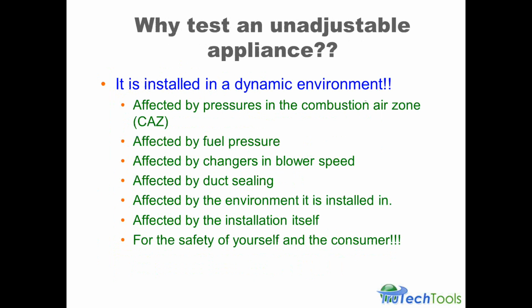Another question we often get is, why would I want to test an appliance that's unadjustable? Many times people consider that, especially residential warm air heating systems, furnaces, are really plug and play, and that couldn't be further from the truth. In addition to having to be installed correctly with the right kind of airflow and the right fuel pressure, real basic issues, you also have to recognize that the equipment is installed in a dynamic environment. There can be changes in the combustion air zone, especially with atmospheric fired combustion. Not so much of an issue with sealed combustion, but atmospheric pressure changes can change the way the combustion system operates. Fuel pressure can change the way the system operates.